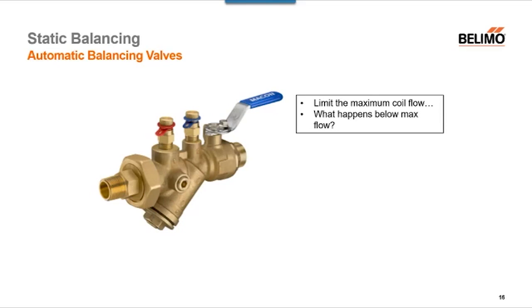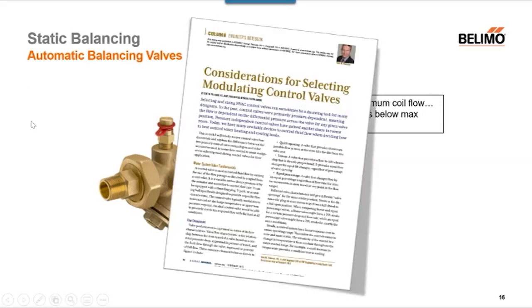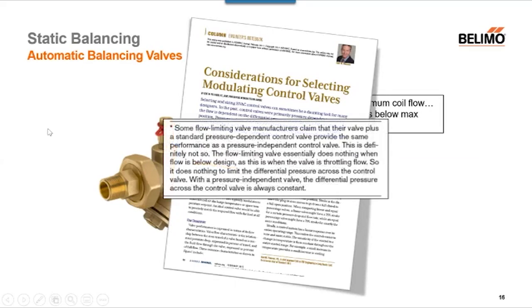Well, let me put it this way. If I have this on a circuit that my coil needs 10 GPM of flow, yes, this will prevent flows greater than 10 GPM going through the circuit. But as an article that was published in the ASHRAE Journal a while ago said, some flow limiting valve manufacturers claim that their valve plus a standard pressure-dependent control valve provides the same performance as a pressure-independent control valve. And I agree with this statement completely.